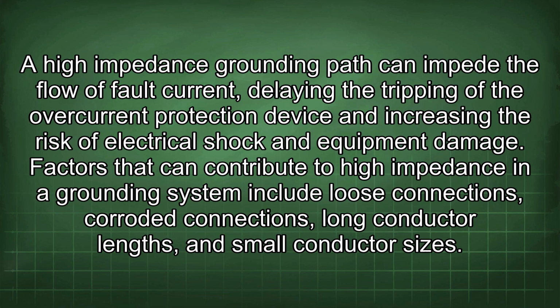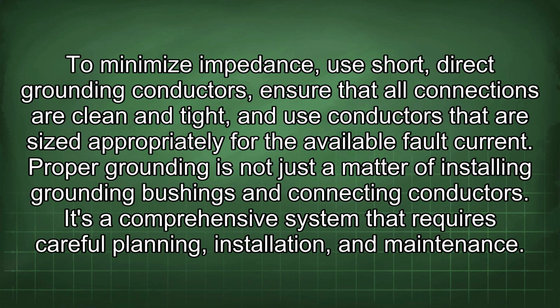Factors that can contribute to high impedance in the grounding system include loose connections, corroded connections, long conductor lengths, and small conductor sizes. To minimize impedance, use short, direct grounding conductors, ensure that all connections are clean and tight, and use conductors that are sized appropriately for the available fault current.